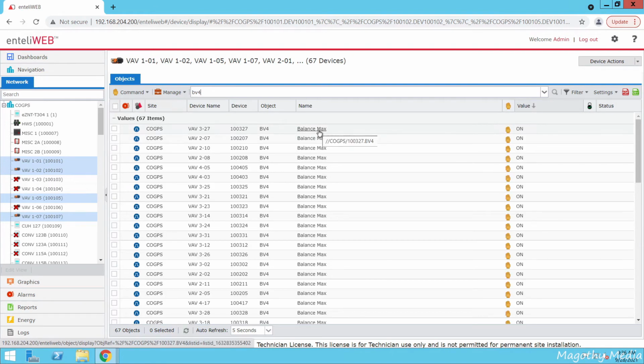They're really convenient points to have during the construction process, obviously for balancing purposes, but also for something as simple as boiler startup, or just pre-boiler startup when we're trying to get flow through the building. Maybe they're doing a water treatment, trying to get air out of the system. When you're asked to command all the valves in the building open, it's just a simple way to do it. But today's video was really about this navigation trick.